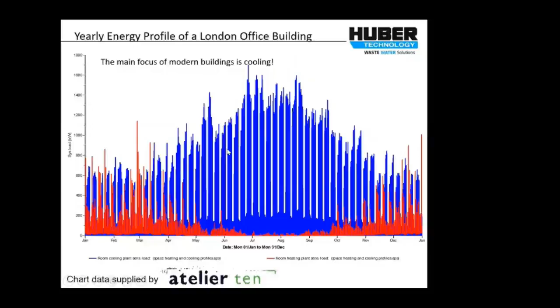So how do we extract low-grade heat from a sewer? Well, you can see here we make a sewer intervention. The sewer intervention is made in the sewer, and we bleed off a proportion of the flow from the sewer. The sewage comes into a screen. I'll show you a screen in a minute, but the screen removes all solids in two dimensions at 6 mil. So it's a 6 mil perforated screen. The screenings themselves are transported up via an auger and discharged back into the sewer, where they can go back to the sewage works. And the screened sewage is then pumped into a building which contains what we call the ROWIN, which is our heat exchanger.